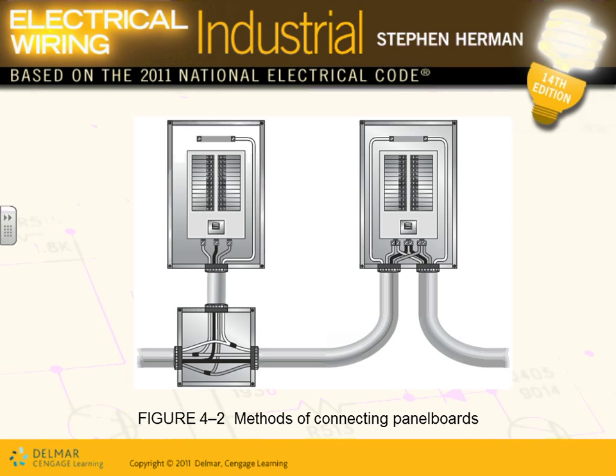The problem with the subfeed is if you have a short circuit right in this area here, what's going to happen to the feeder? Your feeder is down, so you lose all your panels. Any comments, any questions about the subfeed? What's the advantage of this? Cheap installation. You take a 400 amp feeder here and split it into 200 here and 200 here, for example. You take a 600 amp feeder, you split it into 200, 200, and 200.